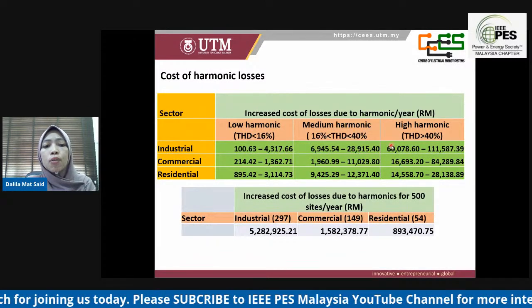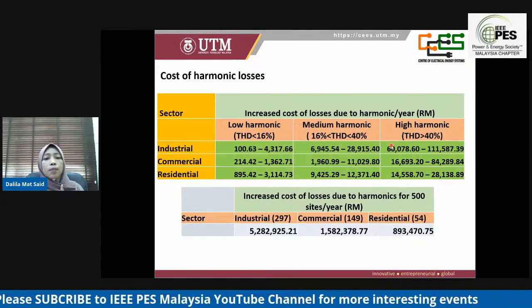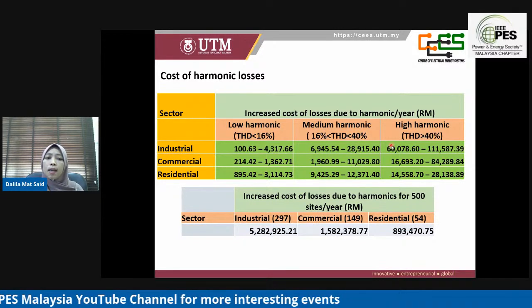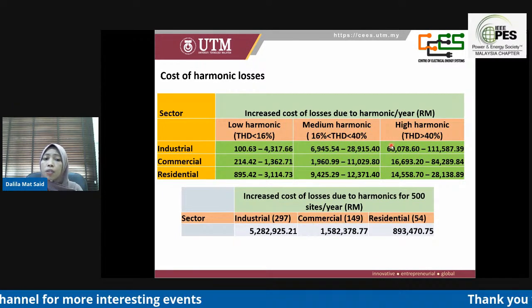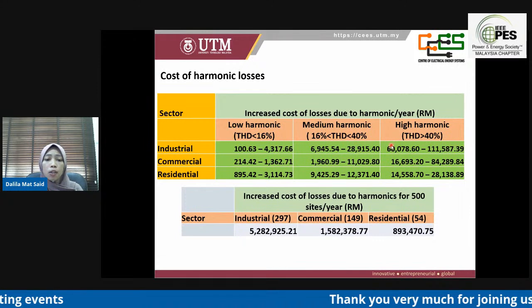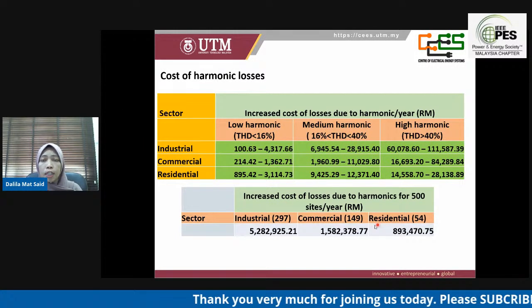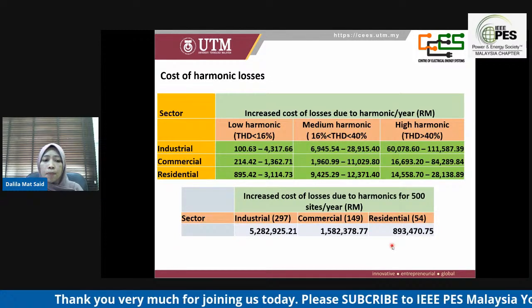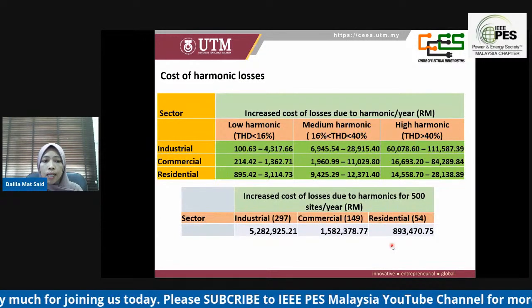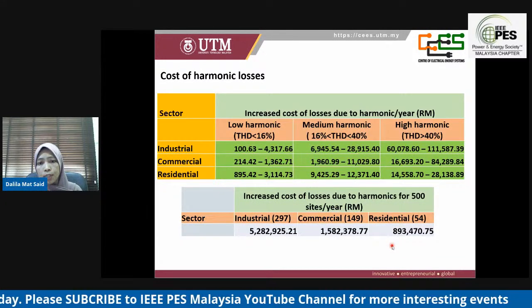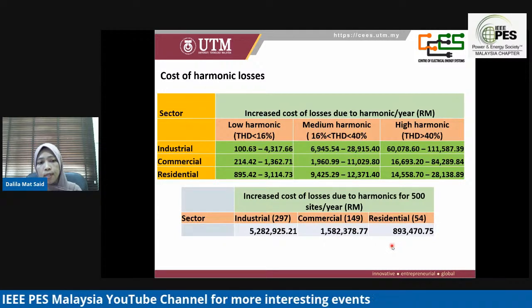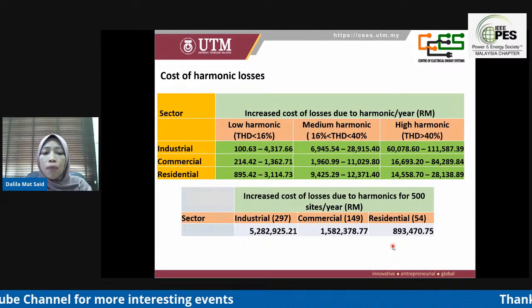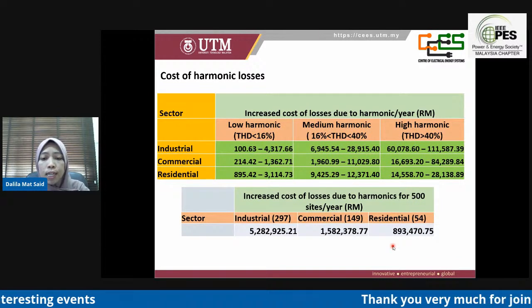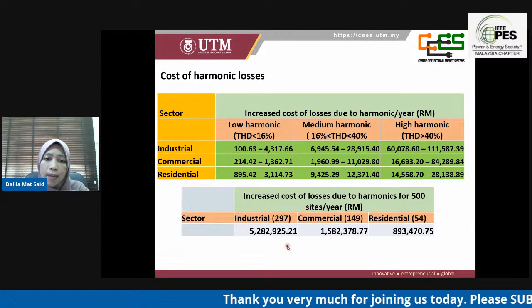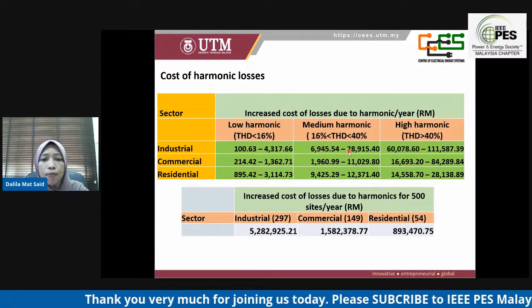Harmonic distortion also has a negative effect on transformer efficiency in addition to other losses. The loss in the distribution transformer affects the price of electricity as well as system losses. The effect on losses has been studied in terms of cost with respect to linear and non-linear load conditions. The expected value of economic damage is divided into operating cost and aging cost, and the total consideration of increased cost of losses and aging costs with the effect of harmonics. So we have categorized the different sectors and the different categories of harmonics.